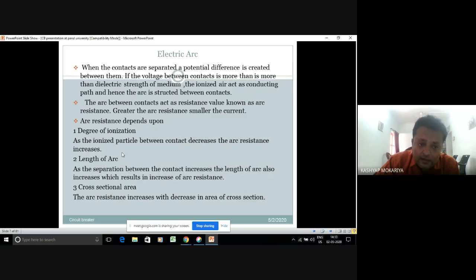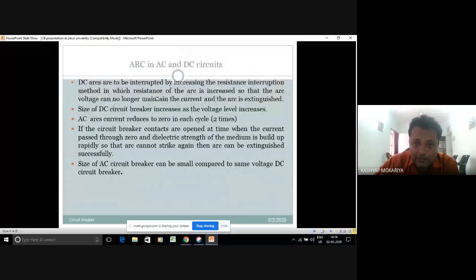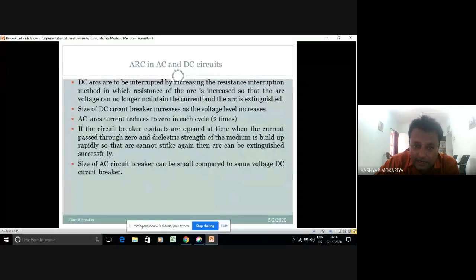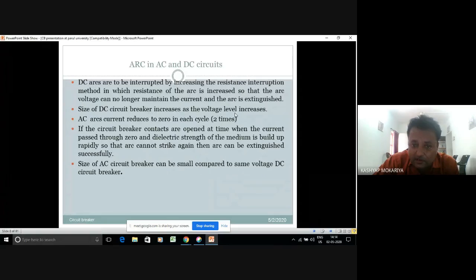So again, I'm repeating, lengthening of the arc, the high resistance interruption method, is used for a 450 volt air circuit breaker, or it can be used for some DC breakers. For the AC breakers, like vacuum breakers and air blast circuit breakers, we are using the current zero interruption phenomenon: when the current passes through zero, we have to build up the rate of rise of dielectric strength. That will definitely take care of the arc extinguishing. So DC arcs are to be interrupted by the high resistance interruption method, and as the resistance of the arc is increased, the size of the DC breaker increases as the voltage level increases.